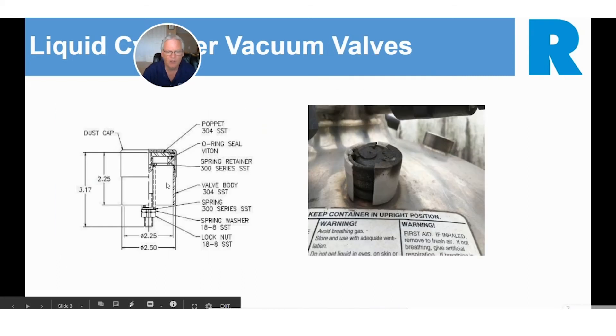Here's a simple tip. All the cylinders now today, all the OEM manufacturers come with a vacuum port welded onto the top of the crown of the cylinder. Some of the earlier ones had a pinch tube design, but for quite some time now, they've all come out with a vacuum port on them. There's some different sizes. If the cylinder's been out for repair, there may be some different vacuum valve diameters. So it's always smart to measure the OD of the vacuum valve to make sure you get the right cap to put back on it.